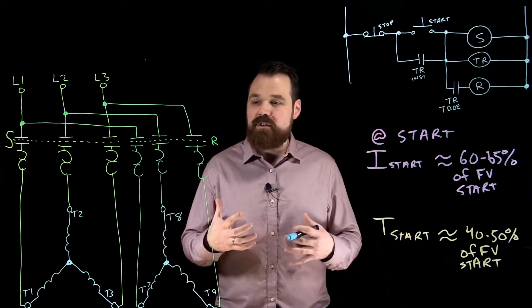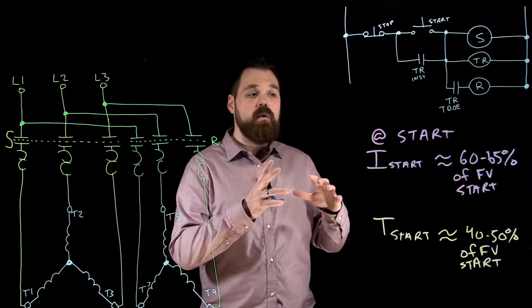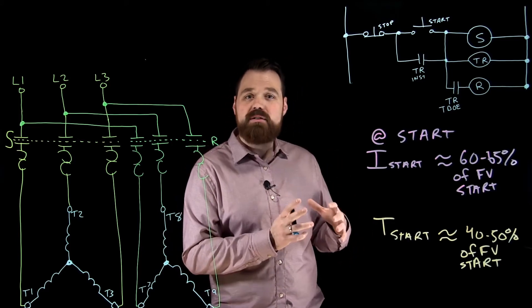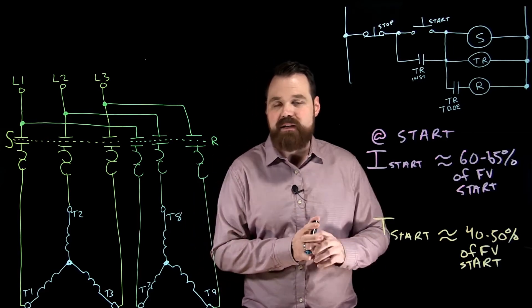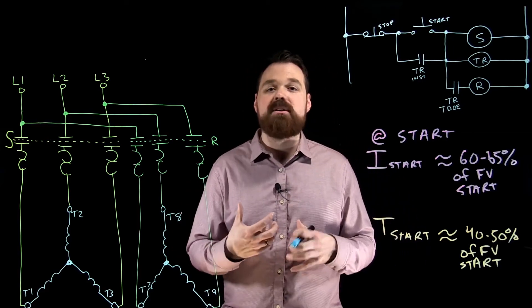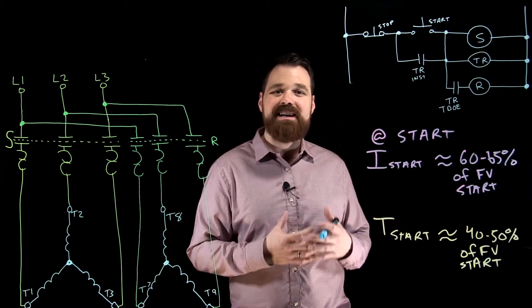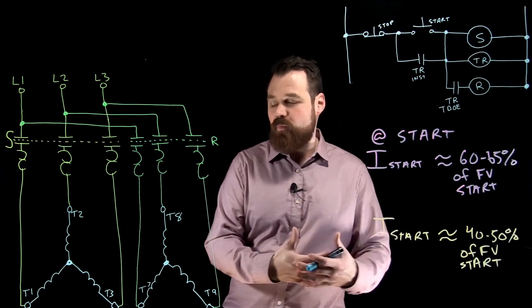The very last thing with these motors is sizing those overloads. We always need to make sure as an electrician or an installer, whenever we're working on these, we size our overloads correctly. When we think about overloads, they're to be used when the motor is running. The overloads do nothing at start; the overloads are for when the motor is running.